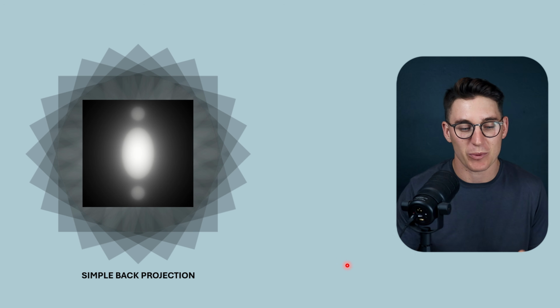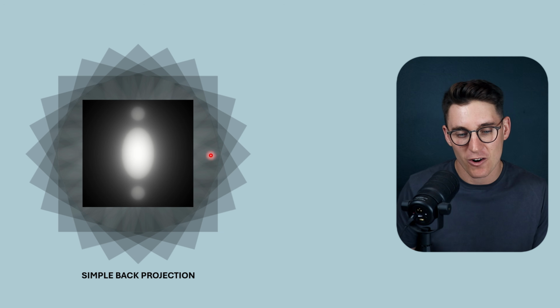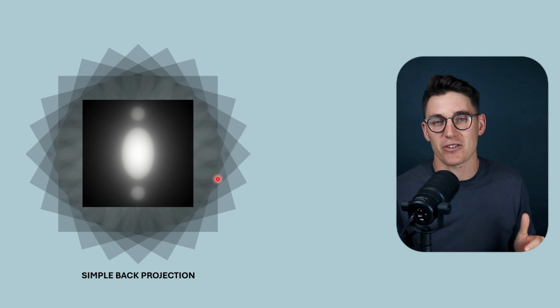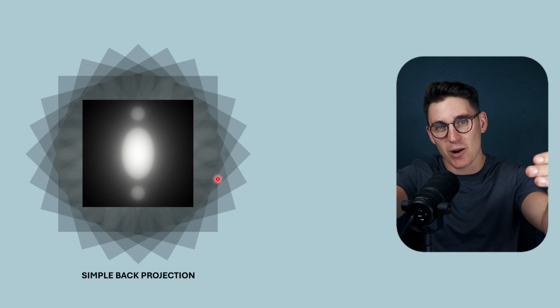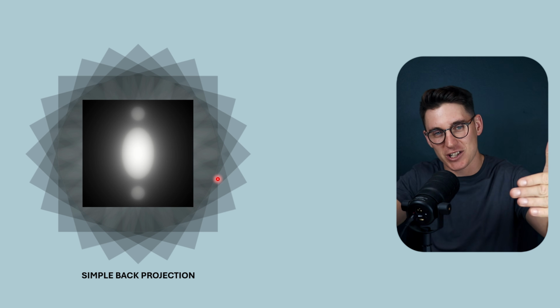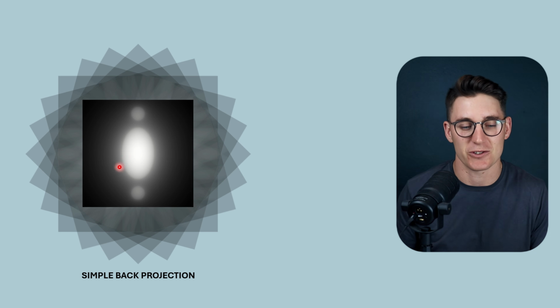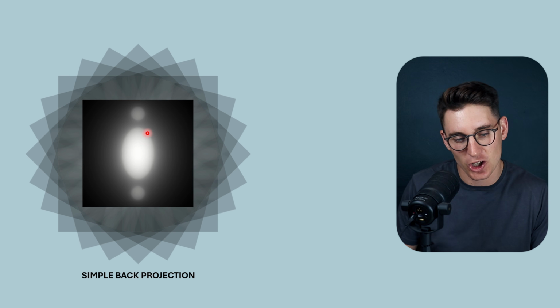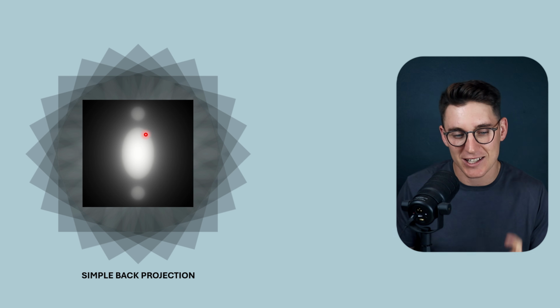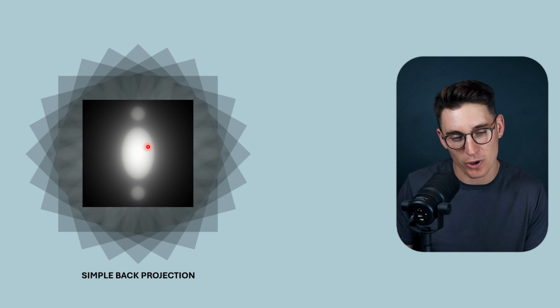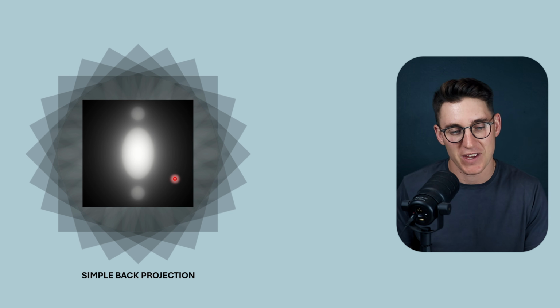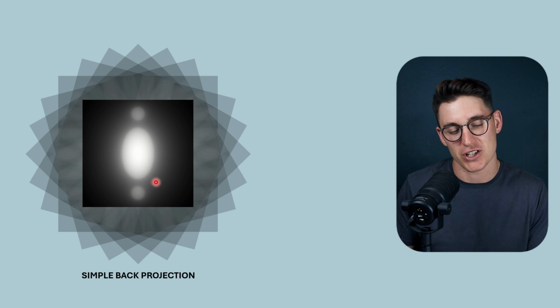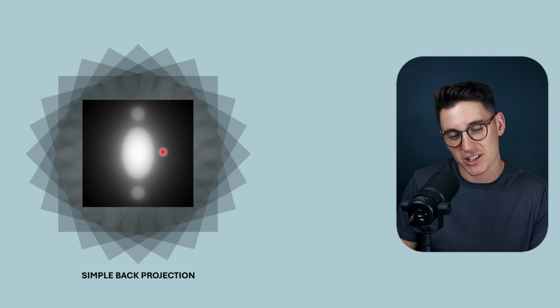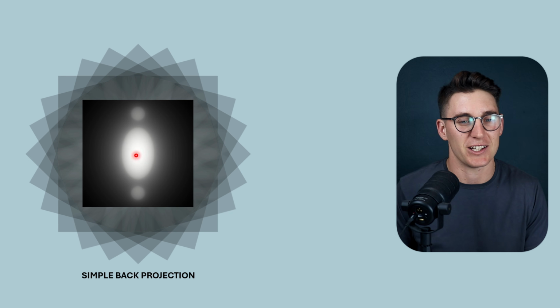So let's revisit the image that we created in simple back projection. Remember, we've got projection data at multiple different angles around the patient, and we're smearing that attenuation data back across these different angles. And ultimately, that data is going to accumulate and form this image here. Now, you can see the major issue with this image is the blurring here. We've got poor edge definition, and we've got a lot of radial blurring occurring from all the attenuating structures here. That's the main downfall of simple back projection. We've got good contrast. What we've got here is what's known as a low pass filter. We're going to cover that later on.